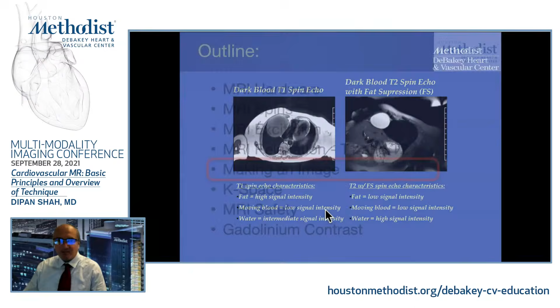So let's talk a little bit now. We've gone through some of the basics. Let's talk about how we manipulate the system to actually make an MRI image. And this now gets to what the purpose of the gradient coils are. The gradients really cause a local alteration to the magnetic field. And as I said, remember, there's three sets of gradients, an X, a Y, and a Z gradient, which means that you can alter the magnetic field differently in each of those three axes.